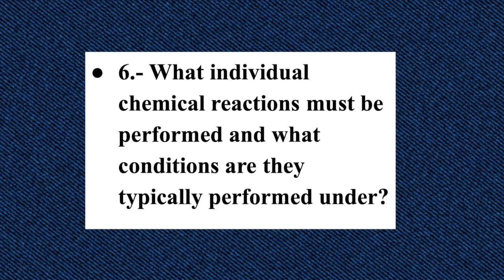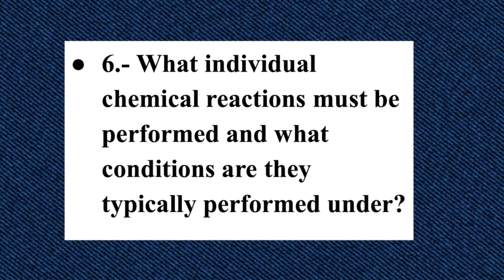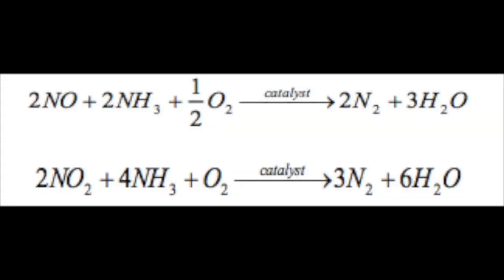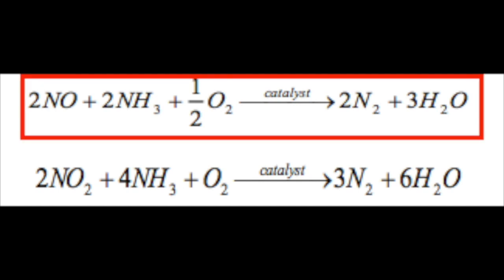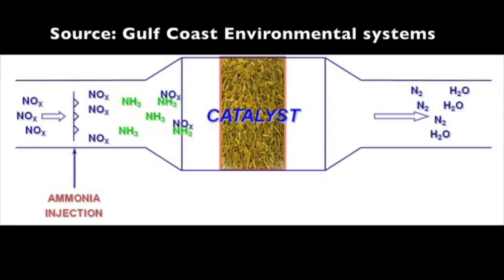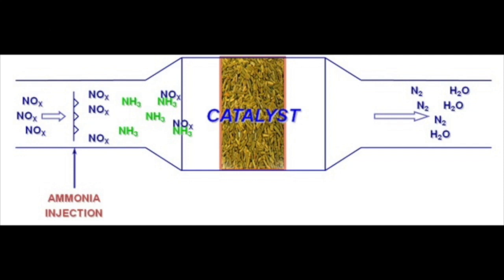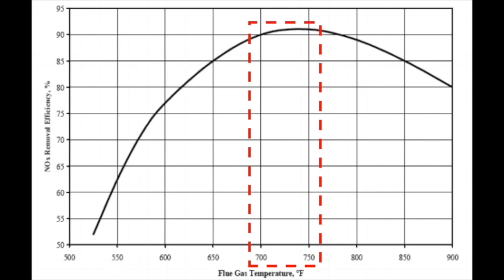Question six: what individual chemical reactions must be performed and under what conditions? As we can see, in both reactions the main chemical transformation is the reduction of nitrogen oxides into nitrogen gas and water vapor. The dominant reaction is the first one, as nitric oxide composes 90% of the nitrogen oxides in flue gas. The reaction is performed after a combustion process, hence conditions are high temperatures between 250 and 430 degrees Celsius, and water vapor is always present and may inhibit the reaction. On this graph, between 700 and 750 degrees Fahrenheit, the nitrogen oxide reduction reaches its maximum values.